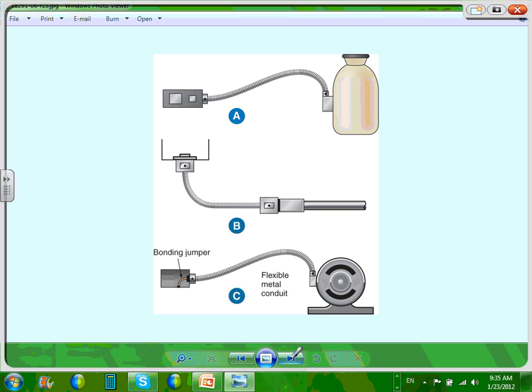But if I have a fan, when you tie to anything that vibrates and moves, then you have to pull an equipment grounding conductor inside it, like this one. So that's the difference between a fixture whip like this, tying it with a flexible metallic conduit, or a fan. For a fan, you have to pull 3 conductors if it's single phase: hot, neutral, and a ground, inside the flex. We talked about this one, guys.